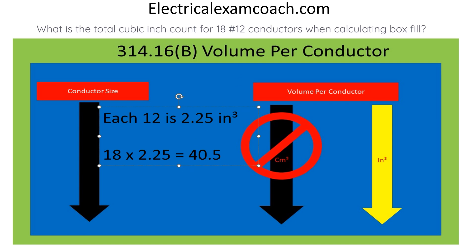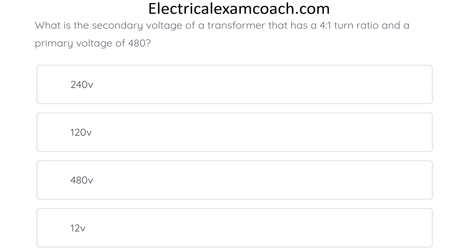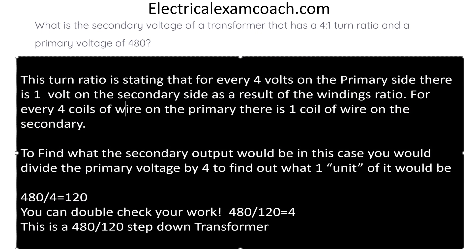What is the secondary voltage of a transformer that has a 4-to-1 turn ratio and a primary voltage of 480? The correct answer is 120. This turns ratio states that for every 4 volts on the primary side, there is 1 volt on the secondary side as a result of the windings ratio. For every 4 coils of wire on the primary side, there is 1 coil on the secondary side. To find the secondary output, you divide the primary voltage by 4 — so 480 divided by 4 equals 120.